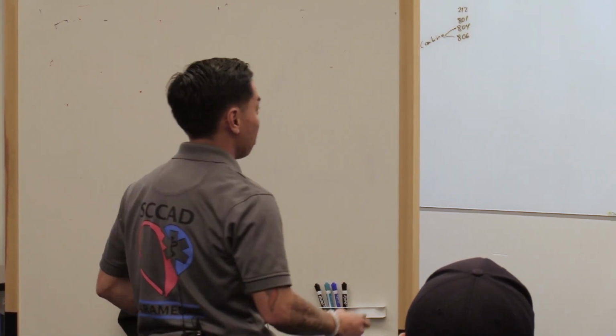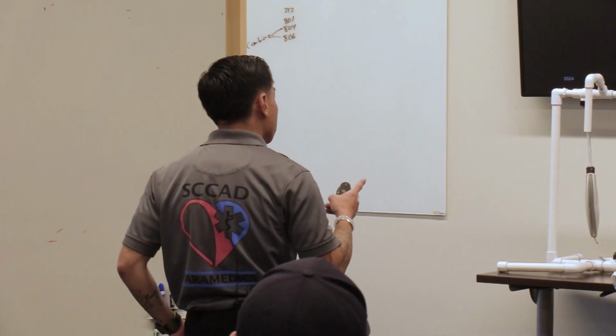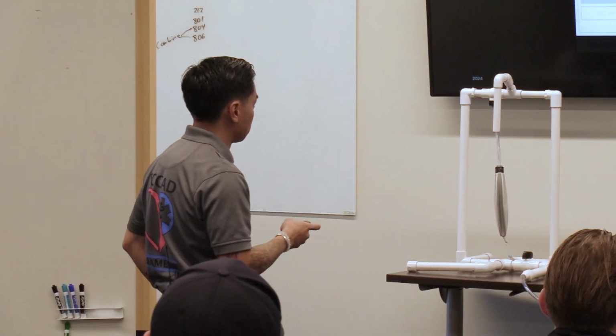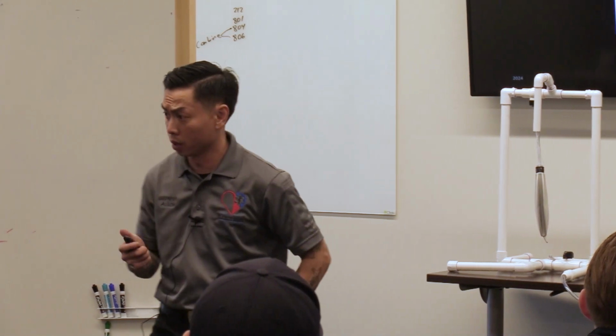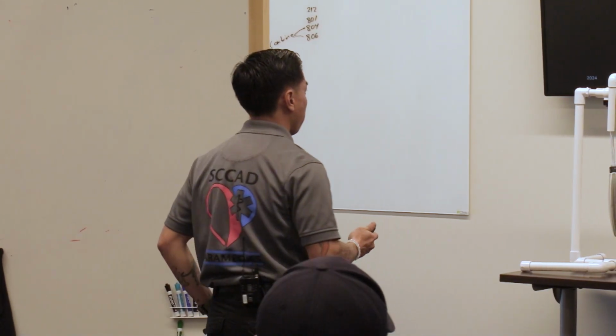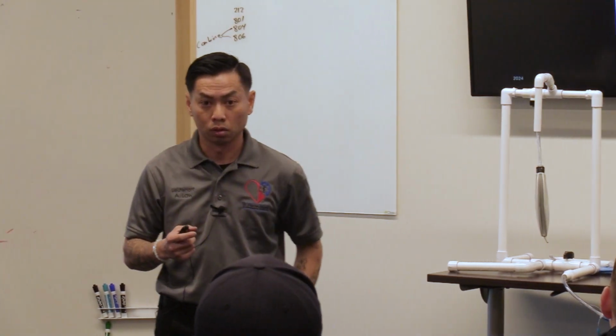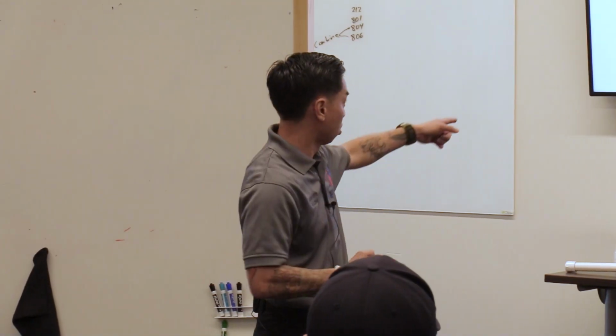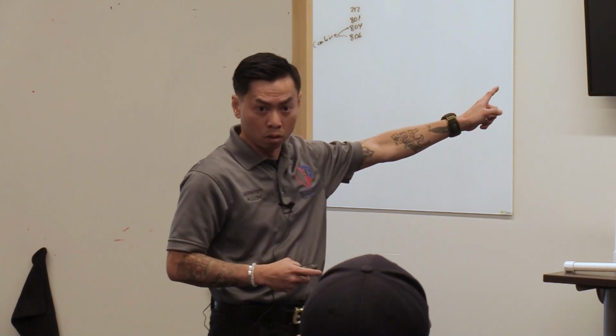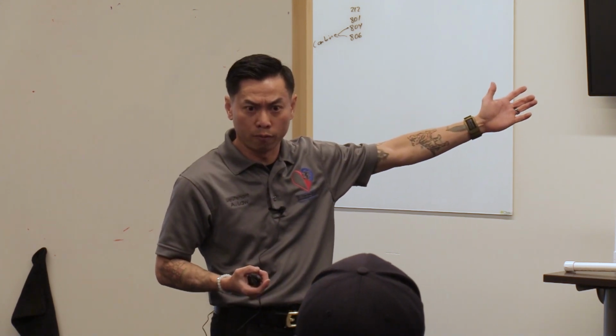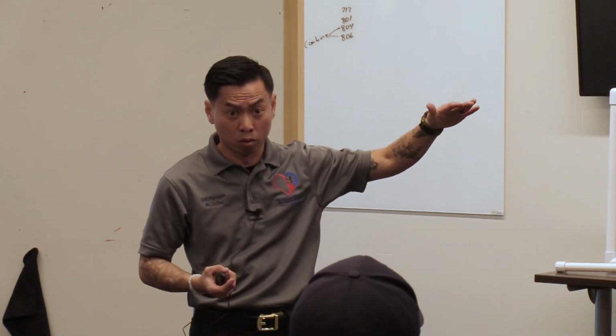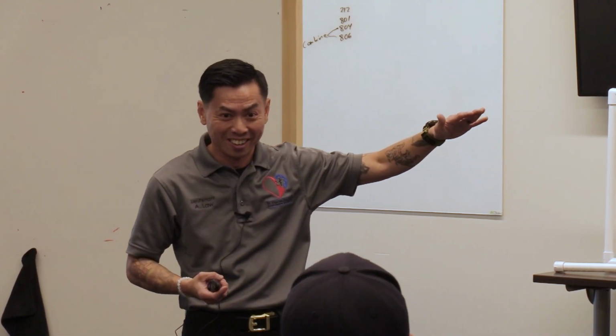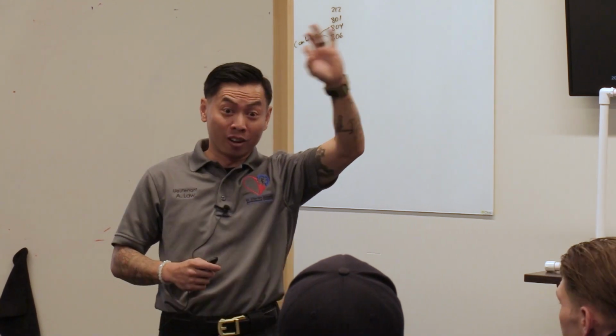So don't worry about that. They didn't let us do it in super user training, so I couldn't even tell you how to do it or what happens anyway. I assume it's just as easy as the other ones. There's probably a picture. So don't worry about that. The 2 things that you really need to be sure of are the leak test and the flow sensor test. And we're confident in that, yeah? All right. If either one of those fails, can you still use it? No. So if you have a red X on either of those 2, you wouldn't want to, right? Because if the flow sensor failed, there are no reliable measurements. The power button is the green one on the upper left-hand side.